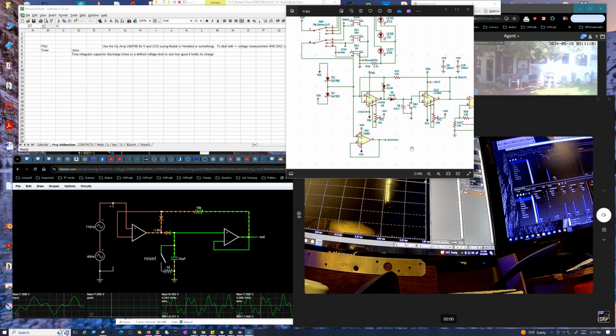So if you got 5 amps, you might generate... well, that's not quite right. On the high end shunt, it was 6 amps per millivolt. For the 500 and the 50, it would be 0.6 amps per millivolt, that kind of thing. My point is, with readings that low, a 1 millivolt difference is significant, and that can be hard to observe on most oscilloscopes. So it's best to have a gain of at least 10, so instead of 6 amps per millivolt, it's 6 amps per 10 millivolts - that's a lot more oscilloscope friendly.